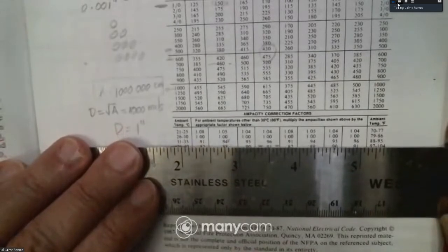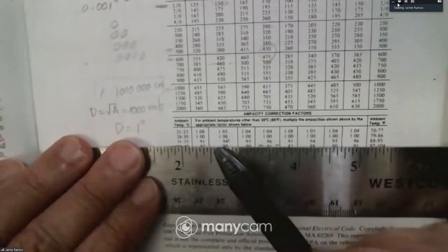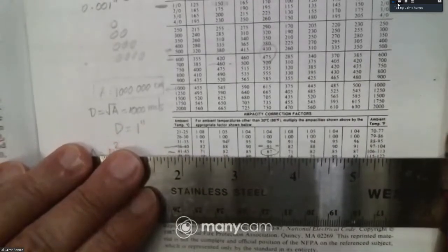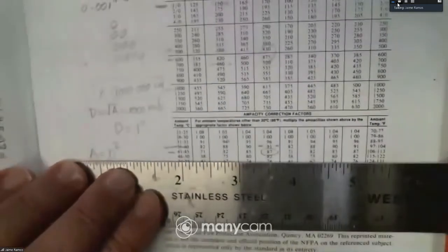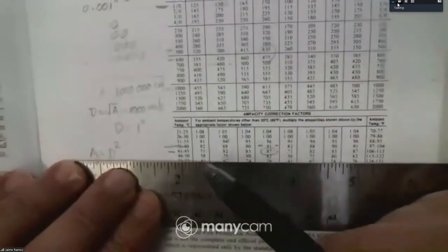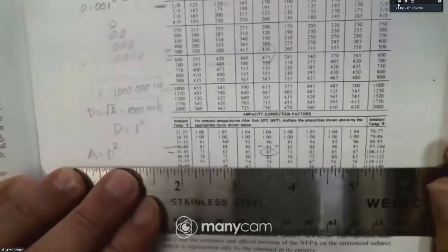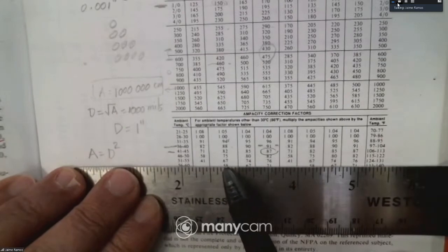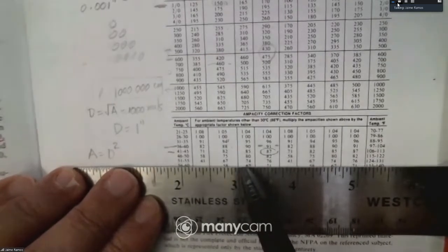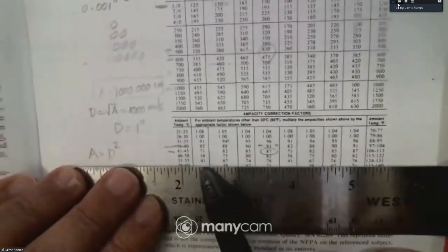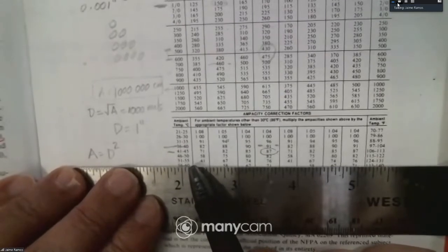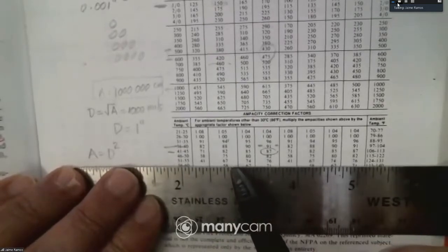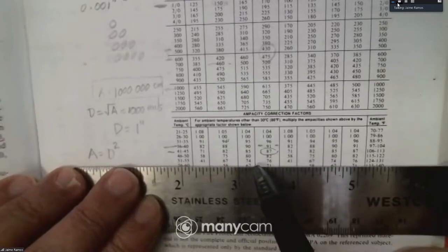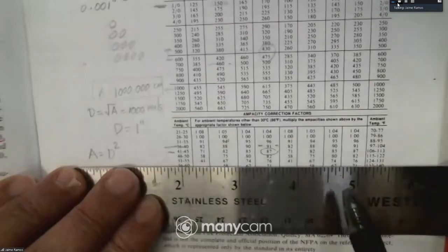However, the opposite is true. As the temperature starts increasing, the correction factors start decreasing, and that's going to have an impact on the ampacity of the conductor. So, for example, if we have on the rooftop a conduit and it's not shaded, if that conduit is under the direct influence of the sun rays, then that conduit may get to a high temperature of maybe 55 degrees, let's say. And then you see how the ampacity of the conductor drops down to average 50%. Okay, so the temperature of ambient is very important, combined with the temperature of the insulation.